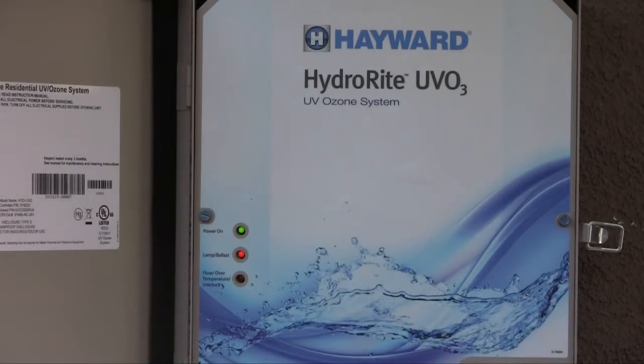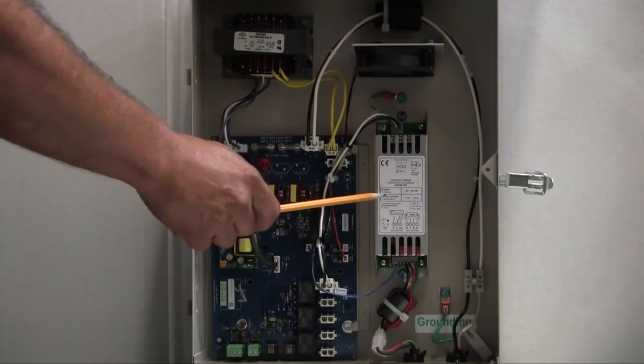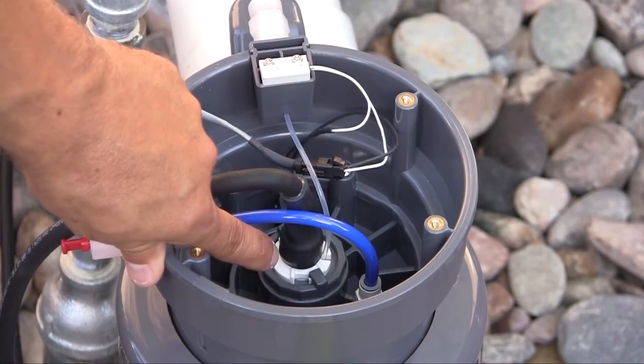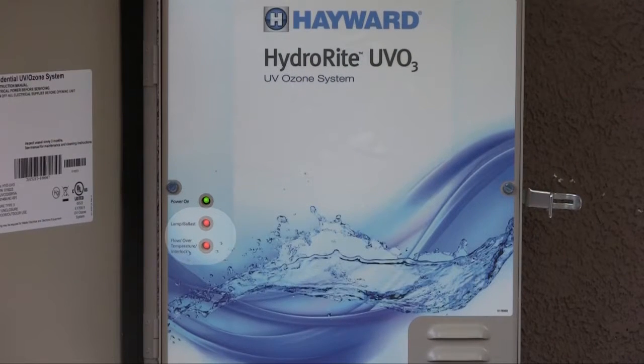This red lamp or ballast LED indicator will come on when there is an issue with the lamp or ballast. It will also light if there is a problem with the connection from the ballast cable to the lamp. Note that the lamp has a defined life and will eventually need to be replaced. We will cover the UV lamp replacement later in the maintenance section of this video. The HydroRite Flow Over Temperature Interlock LED will light along with the lamp ballast LED and the unit will shut down due to the following conditions.